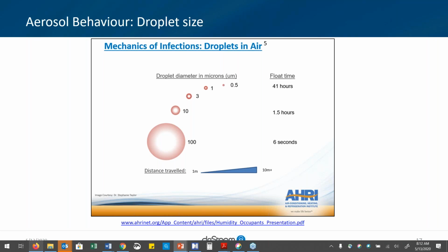In this slide, we see an illustration of aerosol size versus float time and distance traveled. As low RH desiccates the aerosol, it may remain airborne for an extended period of time. Some studies have shown as much as 72 hours. From the perspective of a built environment, we have to consider the capacity of our filtration system to capture small particle size. We should recall with SARS that it was possible for aerosol viral particles to float not only along corridors, but also out of buildings and be pulled into the ventilation systems of adjacent buildings.